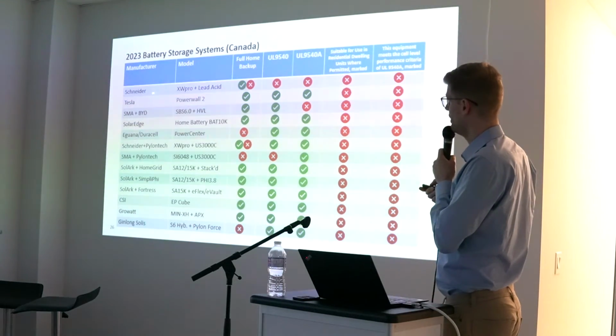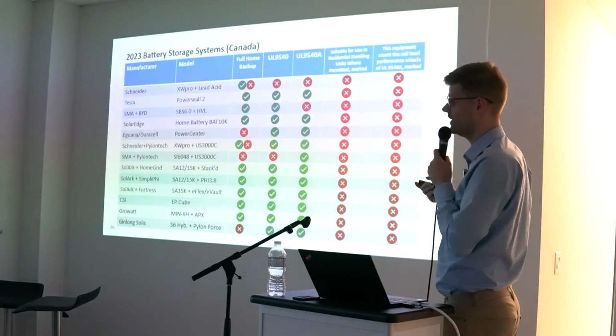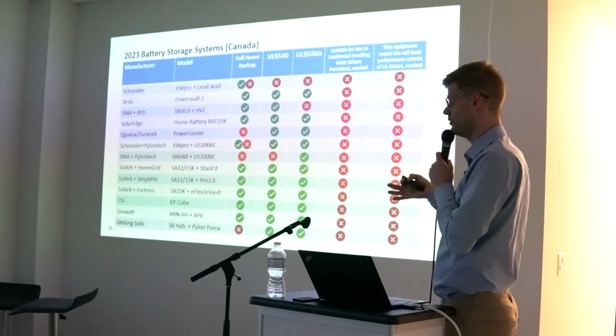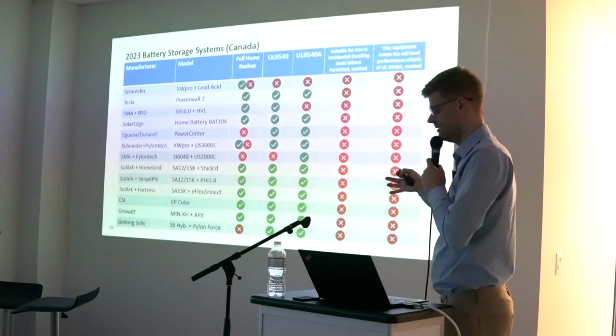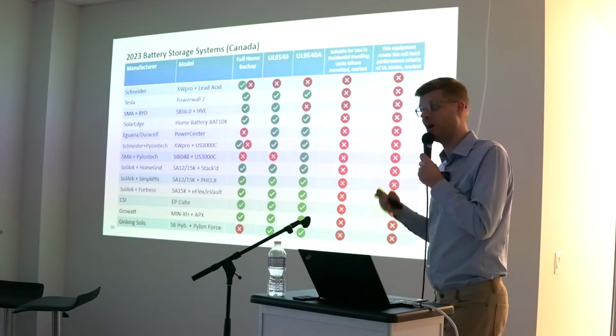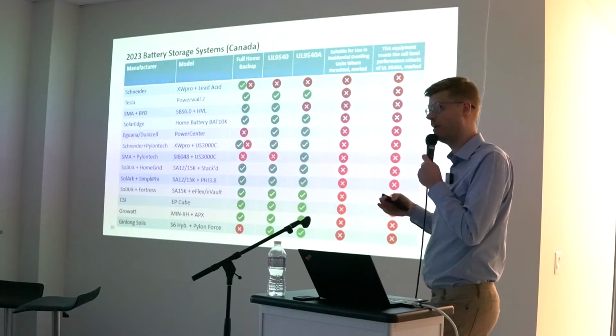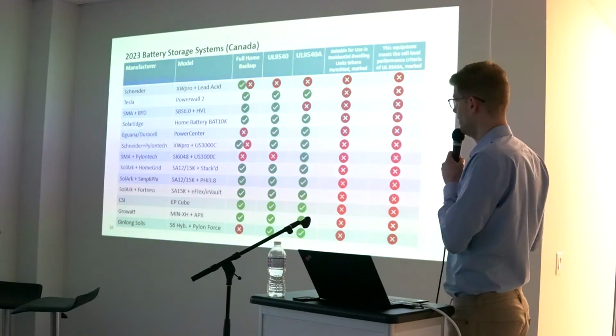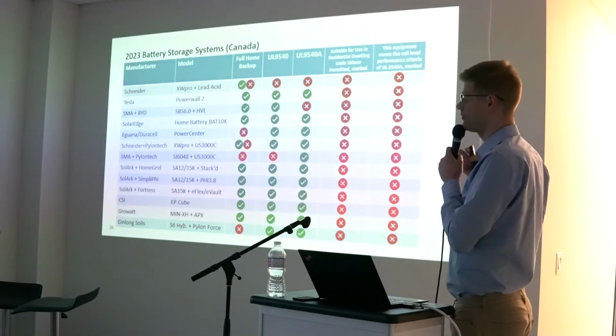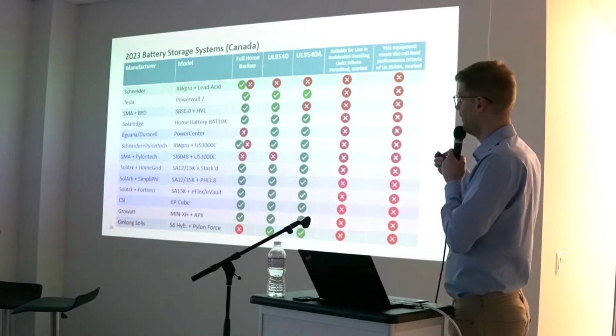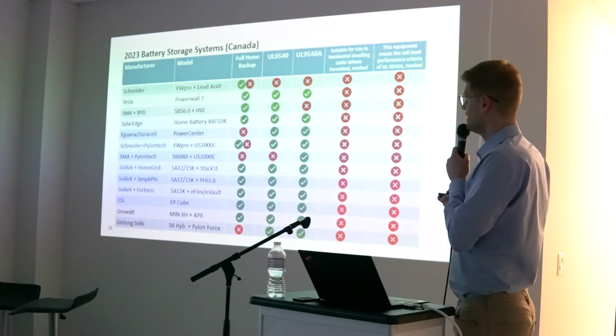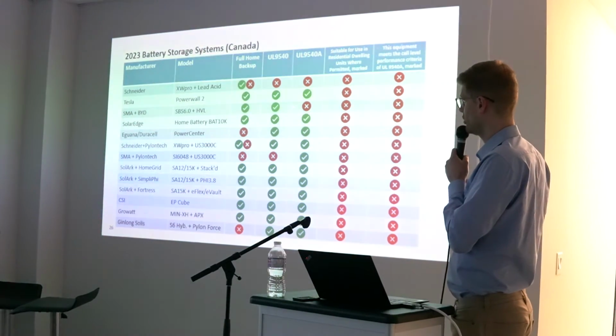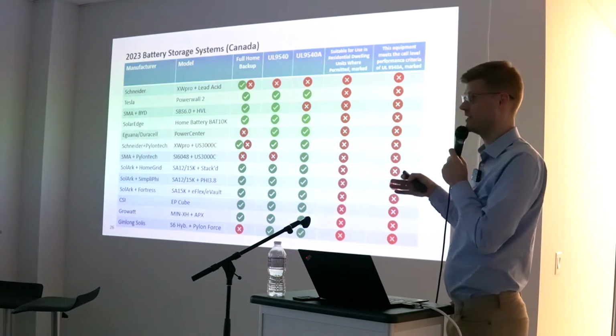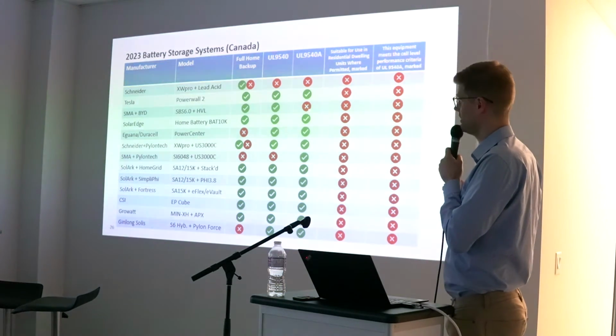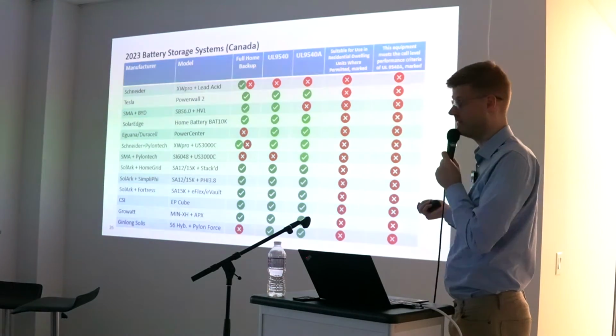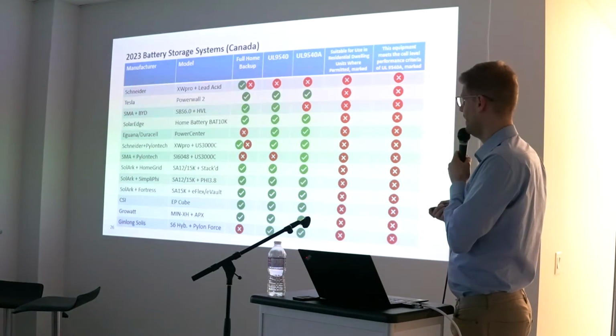The combination of Schneider and lead acid, because lead acid currently cannot be certified to UL9540. The UL group that defines the standards is currently working on a testing method for UL9540A for lead acid, but that's not the case right now. So all the typical off-grid systems are not falling under that system certification. The SMA system with BYD currently has UL9540 in the 2016 version, but the BYD battery doesn't carry the UL9540A fire propagation testing.